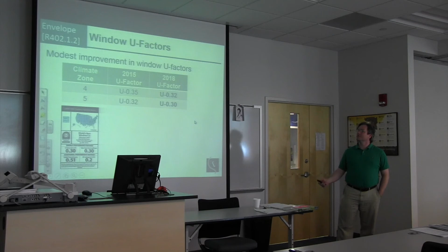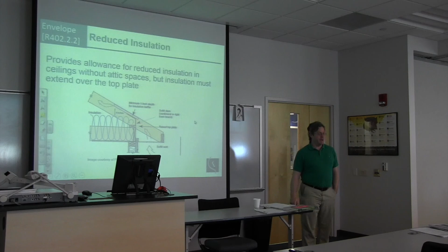Window U factors have a slight improvement here. If you have full depth insulation, or if you're taking the provision to allow a reduced insulation depth, that reduced depth has to go all the way across the top plate, usually with a high-heel truss. Yes, full depth all the way across the plate.